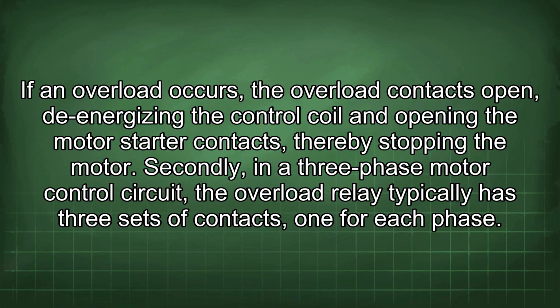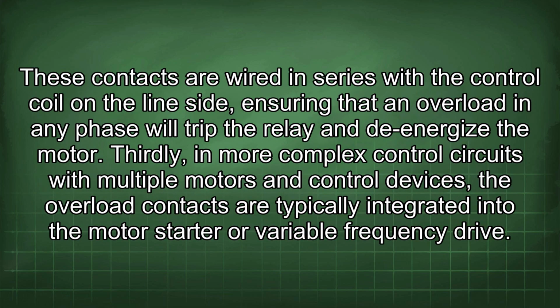the motor. Secondly, in a three-phase motor control circuit, the overload relay typically has 3 sets of contacts, one for each phase. These contacts are wired in series with the control coil on the line side, ensuring that an overload in any phase will trip the relay and de-energize the motor.